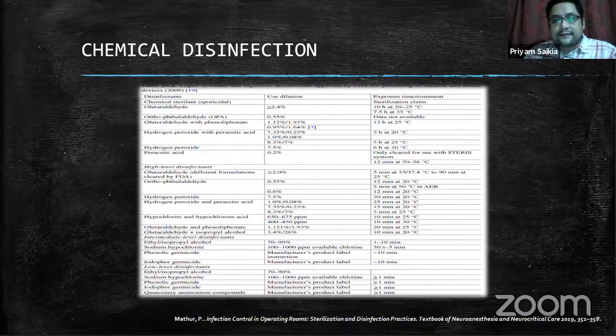I'm extremely sorry, it's a very busy slide, but if we look into the columns of the slide, we see the name of the disinfectant. The disinfectant can be used singly, or in combination with another disinfectant. There are various dilutions or concentrations of these disinfectants available, and for each dilution or concentration, the exposure time is different. Therefore, it is recommended that every facility should have a written policy regarding which disinfectant is to be used, at what dilution, for how long, and for which equipment. Otherwise, it becomes very confusing.